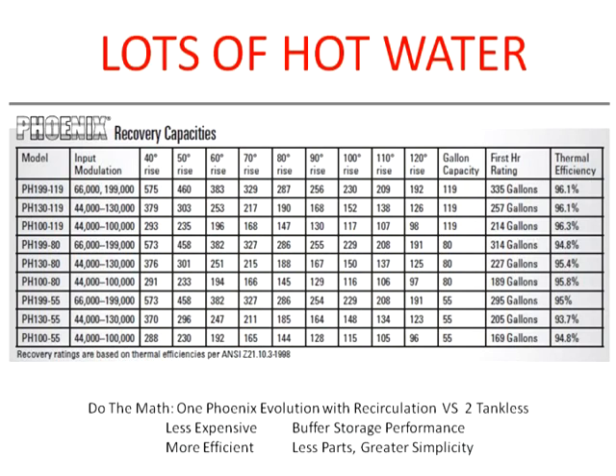You see these jobs with 2 tankless water heaters and a boiler or some other device, and first of all, it's less expensive to put in a Phoenix. It's more efficient, and even look at the pricing of actually putting a boiler and a condensing tankless together, all of that piping, and you're going to find this is less expensive. And we'll touch on that more. So there are the charms of the buffer, and it's very high domestic hot water production.